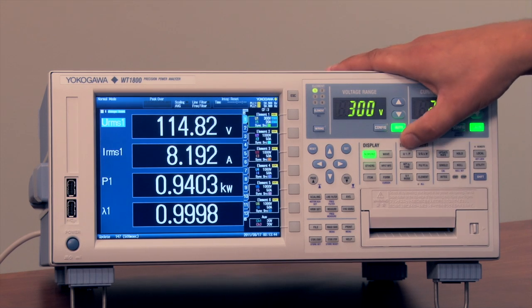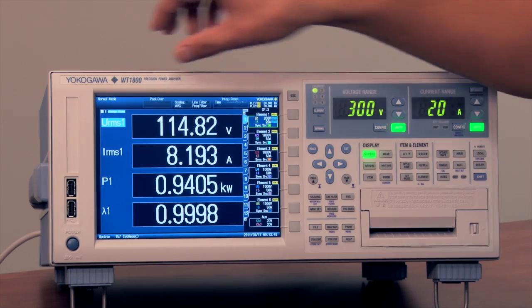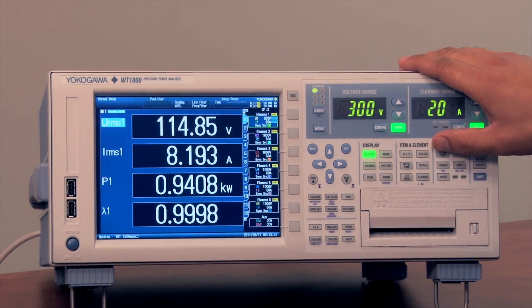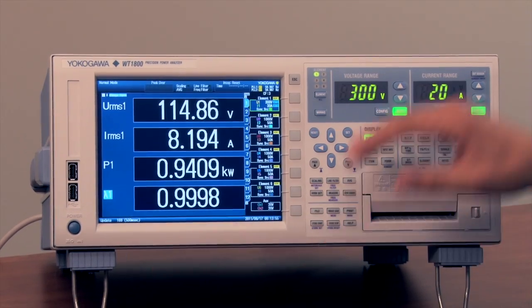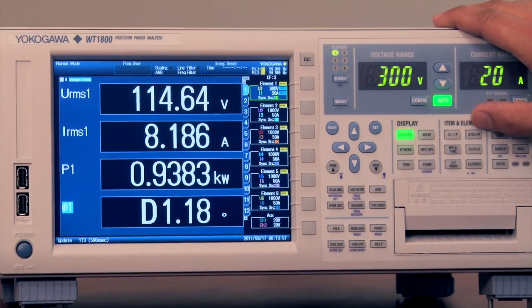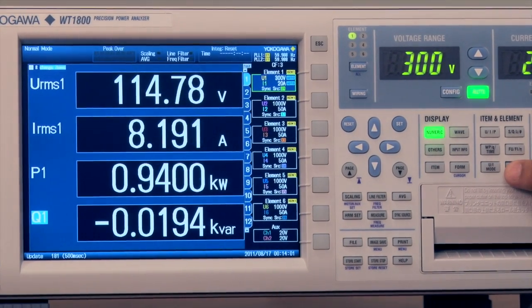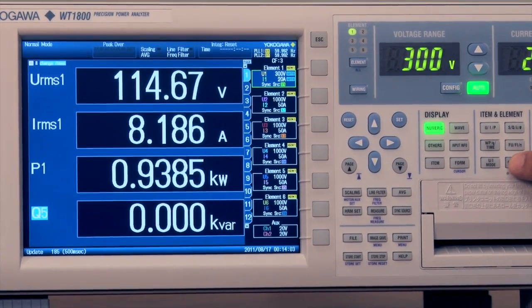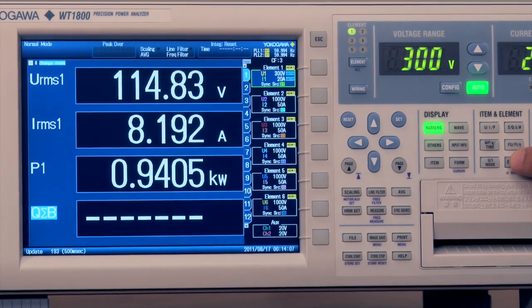Each key is labeled for voltage, current, power, apparent power, reactive power, power factor for example. So I can easily pick my target measurement. In this case let's say if I want to change power factor, I can change that to any of, let's say, apparent or reactive power, and the target element I can even change that to any of the other six or even a summation if I was doing a three-phase application.